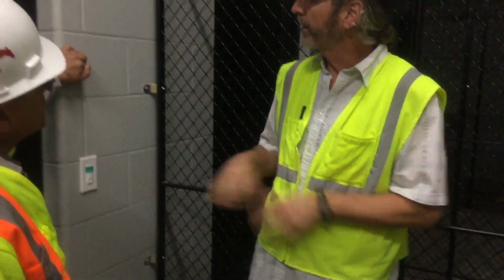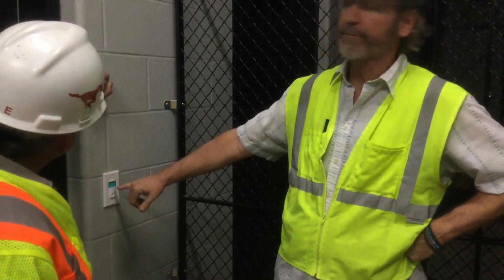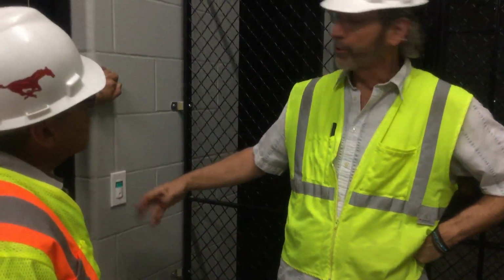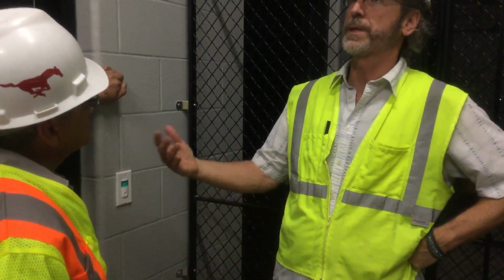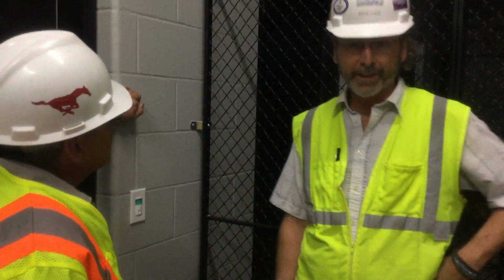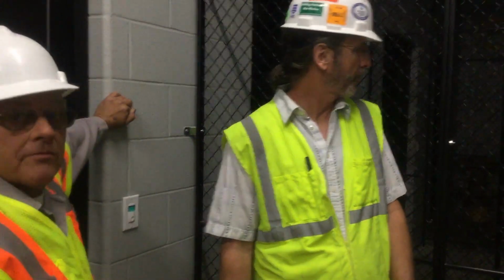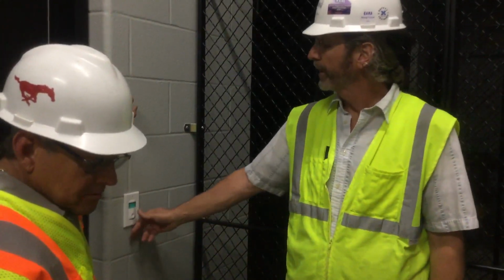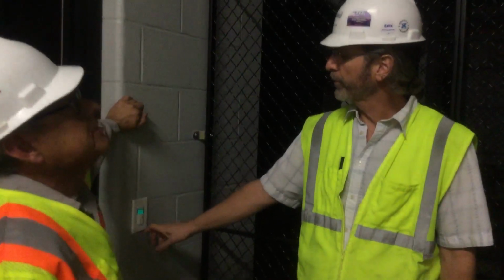That's the idea. Notice I just reset it to 25 minutes instead of 3 hours. So you may decide that you'd rather these equipment cages be set for 5 minutes rather than 3 hours, but 3 hours is the default. You can always turn the lights back off whenever you want, and it will stay off.